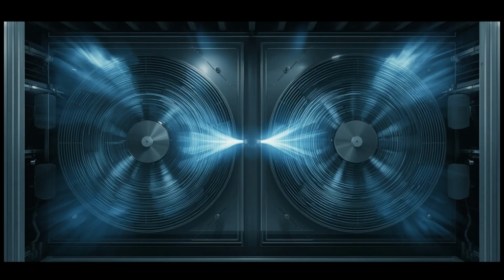Past the damper, the duct opens into a much larger space, tall enough in places to stand inside, wide enough that the sound of the mechanical room seems to soften and spread out, filling the whole volume evenly rather than pressing in from any one direction.